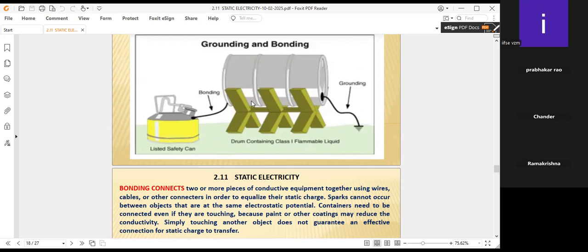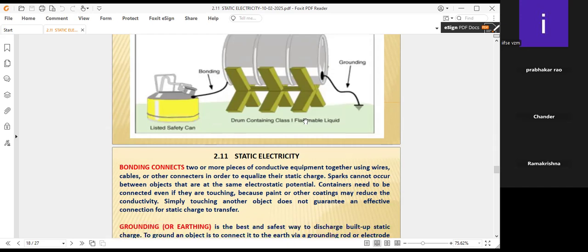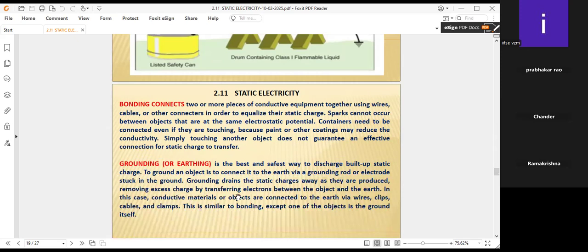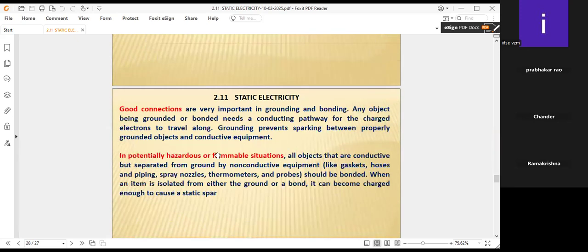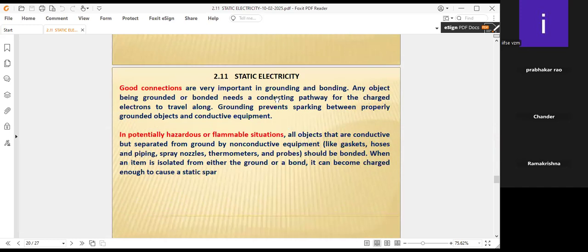Sometimes the static charge imbalance cannot be visible. Only the charge imbalance is there. That's why, in order to prevent leaks and explosions in flammable liquids, bonding is important. Grounding or earthing, as well as bonding, is also important where flammable liquids are there. For example, if you see the good connections, they are very important. Potentially hazardous flammable items like gaskets and all these things.